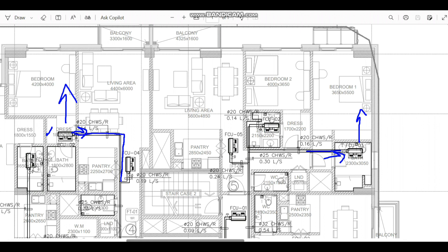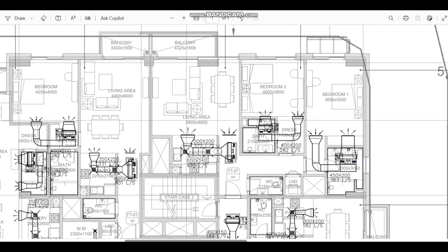For example, if a connection is coming and needs to connect to the right side of the FCU but I didn't order the FCU with the correct chilled water connection side, I would have to reroute the piping with extra elbows — potentially three elbows instead of one. If you have a project with 500 to 600 FCUs and don't consider this, it results in additional fittings, pipes, and supports — all unnecessary expense. So you must consider whether you need the chilled water connection on the left side or right side of the FCU.